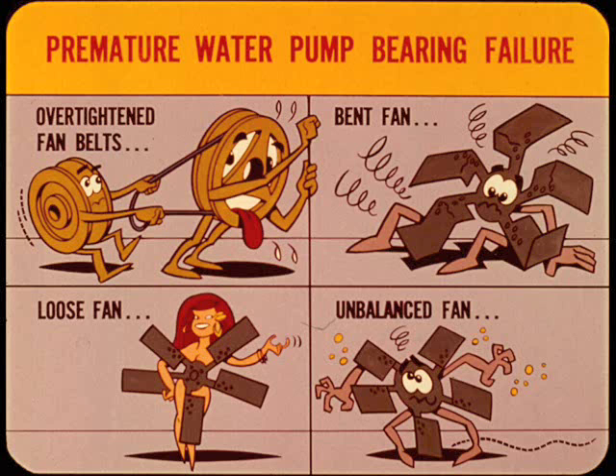In the same area, if the water pump bearing fails prematurely, it could mean a comeback unless you make sure it wasn't caused by over-tightened fan belts or a fan that is loose, bent, or unbalanced. A water pump bearing will not last under these conditions.